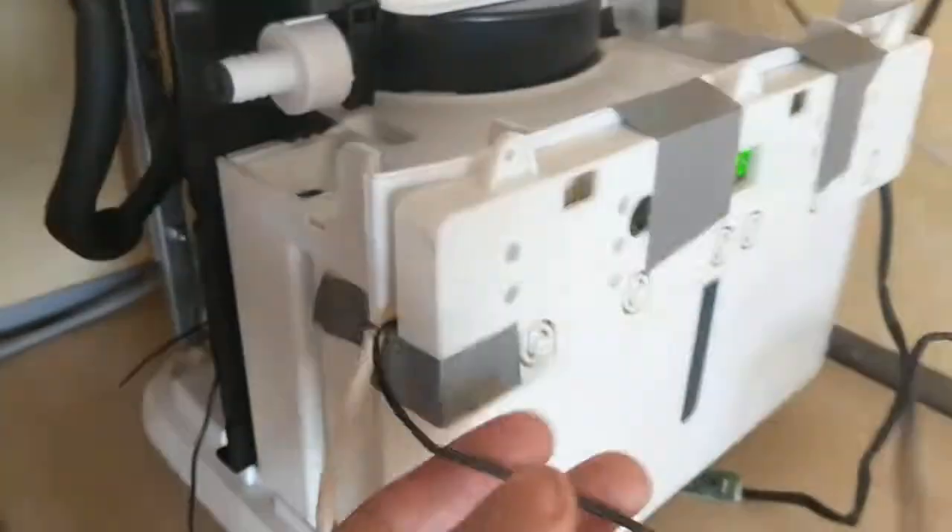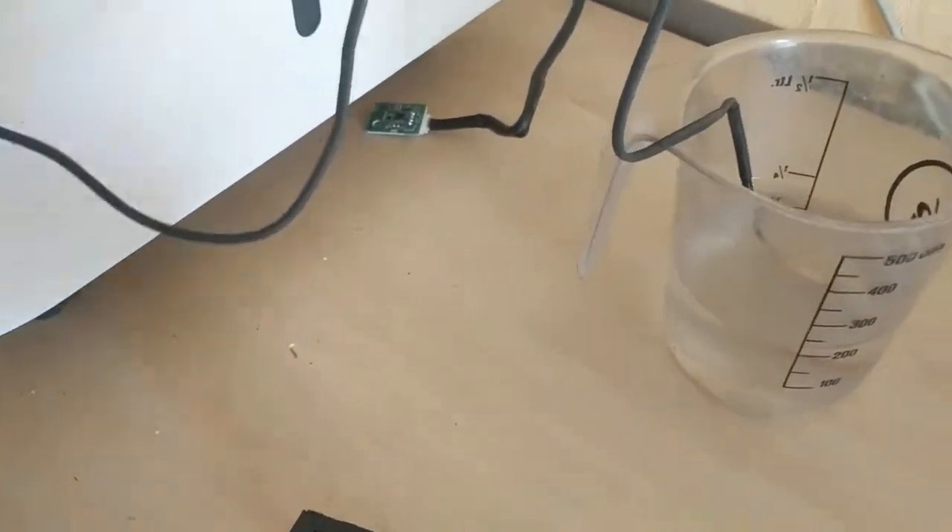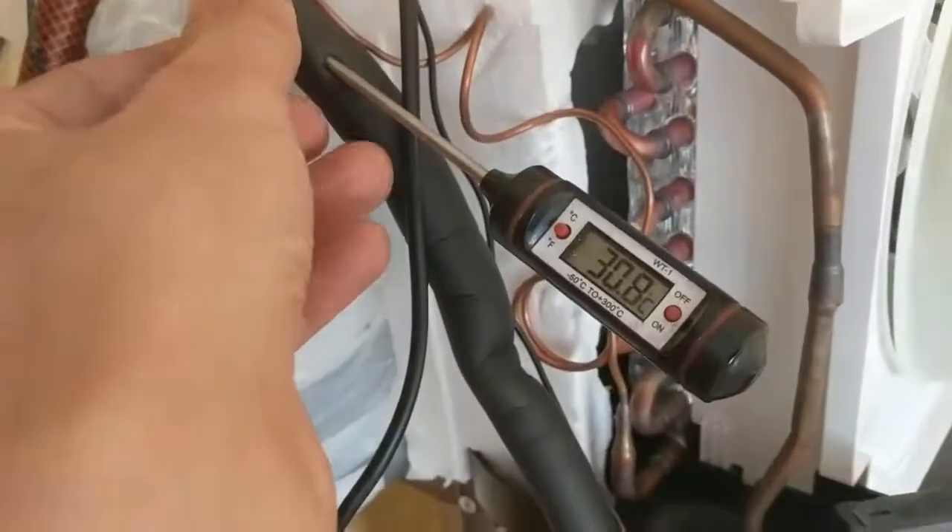I was a bit surprised the machine stops working, because it runs continuously but there's no sensor going to the compressor. The freezer temperature sensor is also at the evaporator, measuring temperature. So this might be a thermal protection inside the compressor itself. It's now shut off and I still cannot turn it on - it turns on every few minutes and then turns off again.